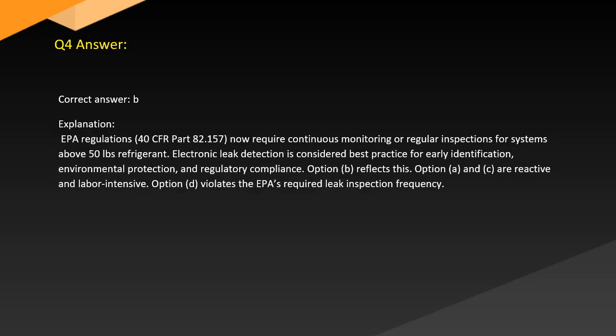Answer. Correct answer: B. Explanation. EPA Regulations 40 CFR Part 82.157 now require continuous monitoring or regular inspections for systems above 50 pounds of refrigerant. Electronic leak detection is considered best practice for early identification, environmental protection, and regulatory compliance. Option B reflects this. Options A and C are reactive and labor-intensive. Option D violates the EPA's required leak inspection frequency.